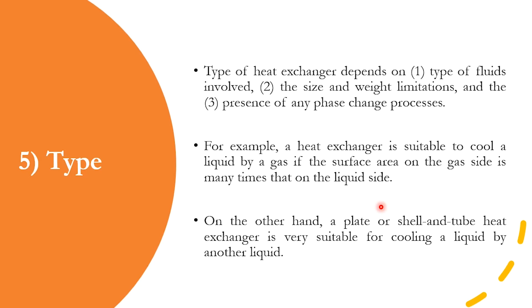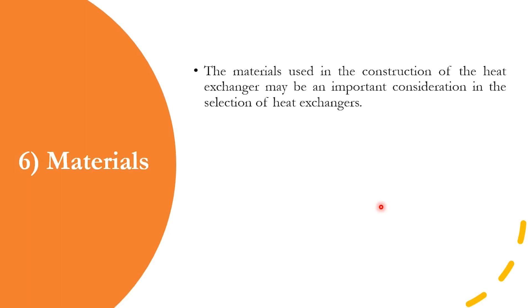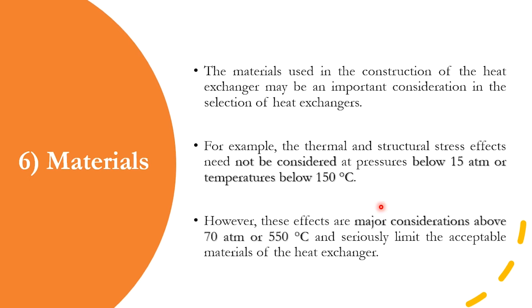Materials of construction play a vital role in heat exchanger selection and cost estimation. They do not play much of a role when pressures are below 15 atm or temperatures below 150°C, but they are a very major consideration when temperatures are above 550°C and pressures are above 70 atm — and can seriously limit the acceptable materials. Accordingly, there are specific ranges for selection regarding temperature and pressure requirements.